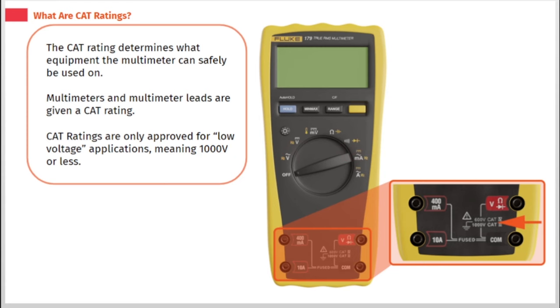The CAT rating determines what equipment the multimeter can safely be used on. Multimeters and multimeter leads are given a CAT rating. CAT ratings are only approved for low voltage applications, meaning 1000 volts or less.